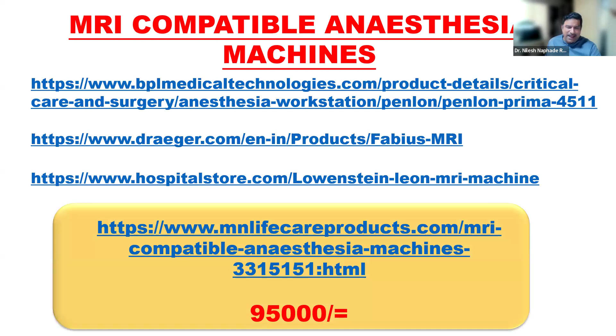MRI compatible anesthesia machines. I have taken good efforts to write down these sites. Please take a picture of this. The yellow window at the bottom is the cheapest, 95,000 rupees anesthesia machine. This is in Indian rupees. And the rest of the machines are 10 lakhs, 9 lakhs, 8 lakhs, 20 lakhs, and the sky is the limit. The 95,000 rupees machine most probably does not have a vaporizer. If you need a Tec vaporizer with that, then that might add to the price.